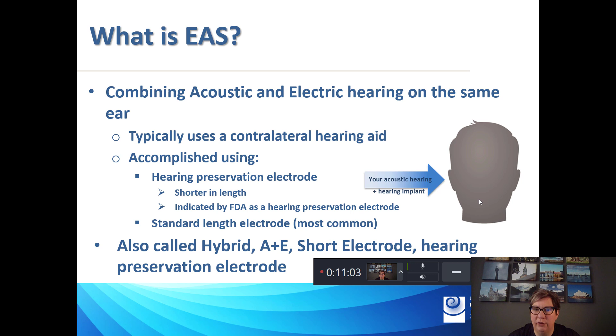So these hearing preservation electrodes, I talked a little bit about the L24. The L24 from the electrode contact here to the electrode tip is 15 millimeters, but if we take it from this part here to the end, it's 16. So it is 22 electrodes, but 4 electrodes on the most basal end of the electrode are often disabled. This is because these 4 electrodes are going to be just right over or right around the round window, and it's going to be part of the ear that is not going to be stimulable.